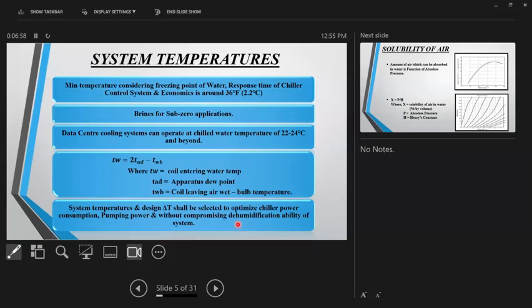A little bit about temperatures. When we talk about chill water systems, usually there is a very narrow band in commercial buildings, but here we are going to talk about a variety of applications. The minimum temperature which we could see in the industry for plain chill water, I'm not talking about brines, clean or pure chill water, is around 2 to 2.2 degrees centigrade. That's the minimum which you can see in the industry. These are special applications, for DM chill water for probably nuclear power plants, etc. There you cannot use brine. So this is the minimum temperature which you can see, 2 to 2.2 degrees centigrade.